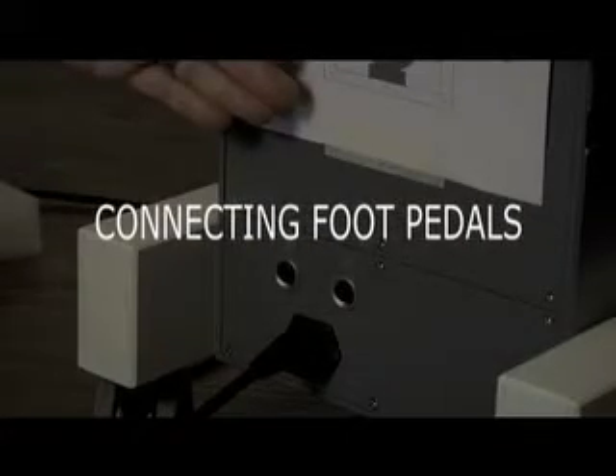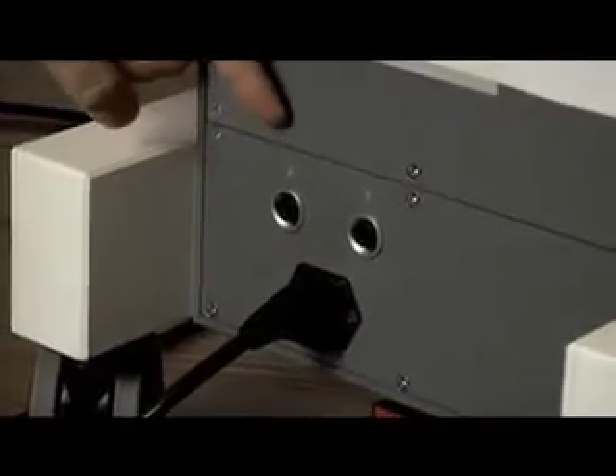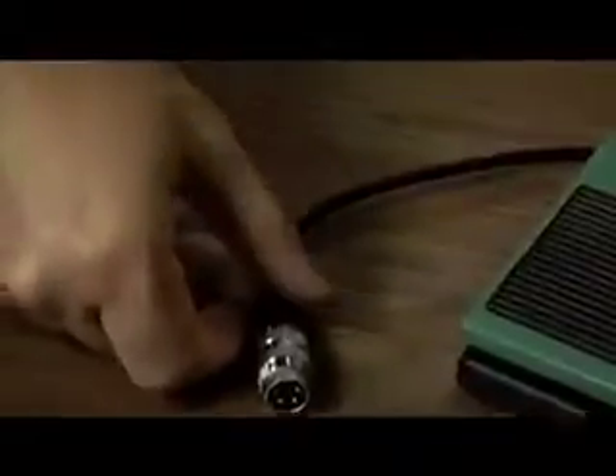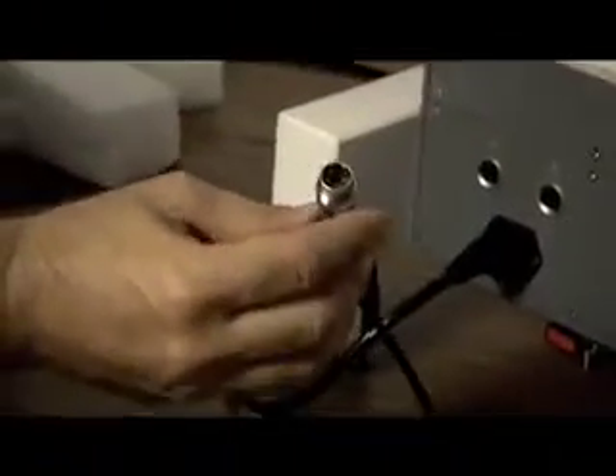Next, connect the power cord to the lower back of the unit and plug it into an appropriate power outlet. Next, connect the 2 foot pedals to the back of the unit just above the power cord. Port 1 is for the harvesting side and port 2 is for the implanting side. Connect the harvesting cable by lining up the small notch on the cable with the notch on the port. Slide it in and screw it down tightly. Do the same with the implanting foot pedal into port number 2. Be careful to line up the notch on the cable with the notch on the port.